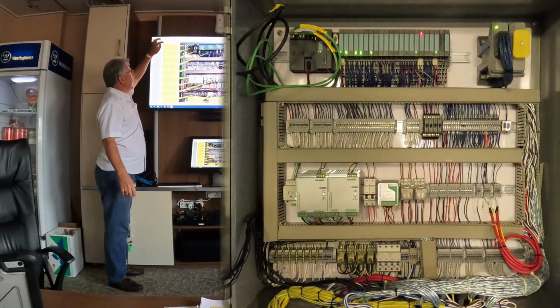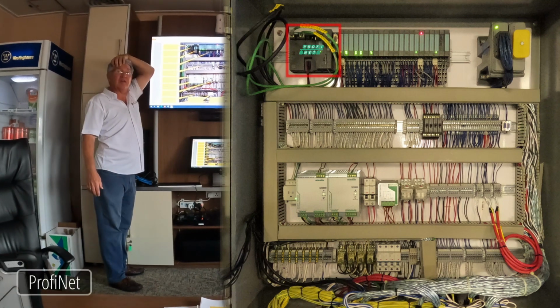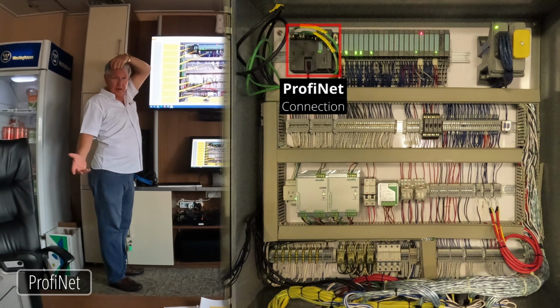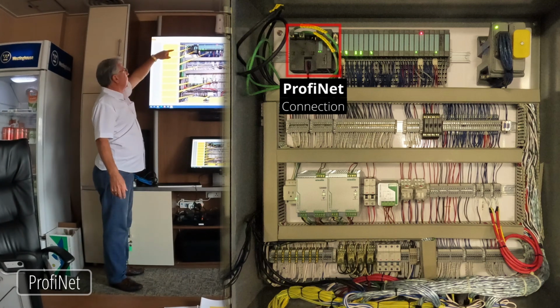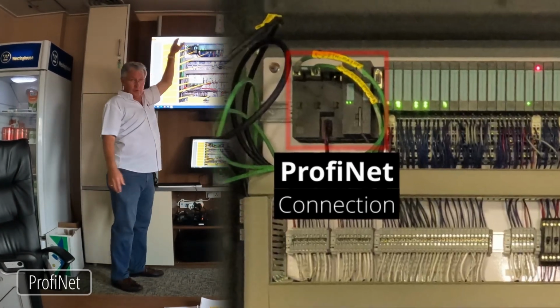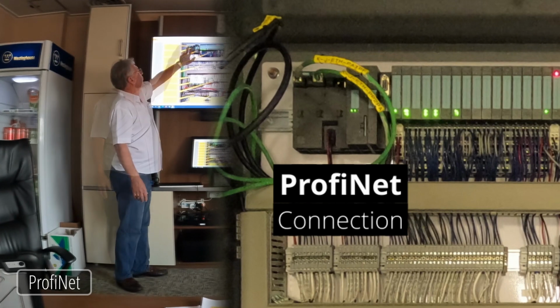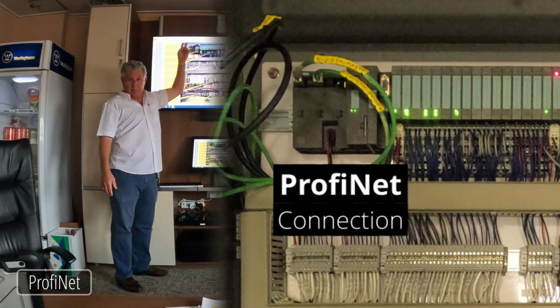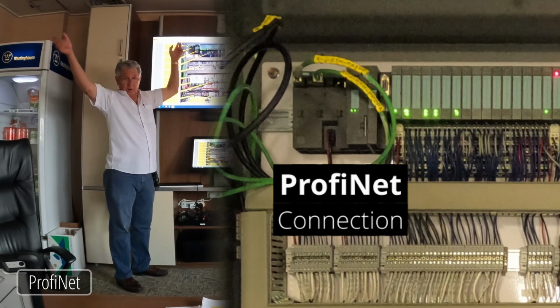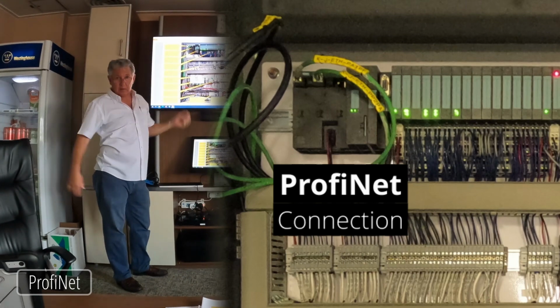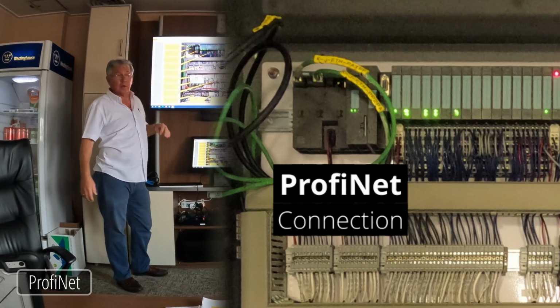That's right, the local leg panel. What do you think this one says? The green color is ProfiNet, it's really Industrial Ethernet. This is one of the connections. If you look closely, you'll see the 2 ports. If these ports were swapped on the green color cable, you'd get an alarm at the control saying the network topology is not correct.